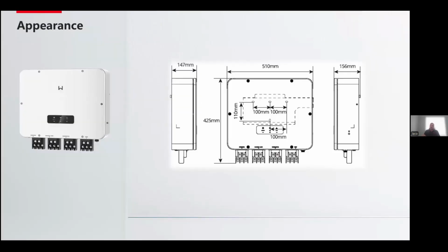Right, so looking at the appearance, again, a very compact unit. It is fully outdoor rated, so it can be installed outside, close to the main incomer, as mentioned. It is a compact design, and it also neatens up the installation because, in this sense, all the heavy AC cables will be going to this point. And the E250 inverter will be installed closer to the battery bank and closer to the PV input. This unit weighs only 17.5 kilograms, so very easy to mount and to manage by a single installer.